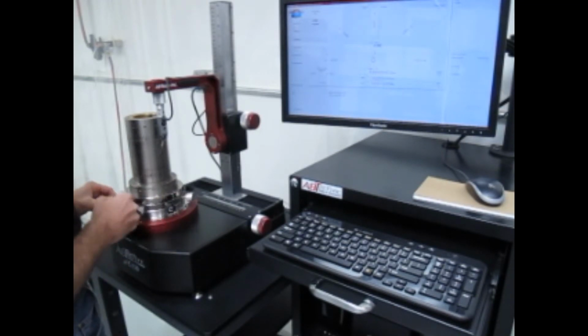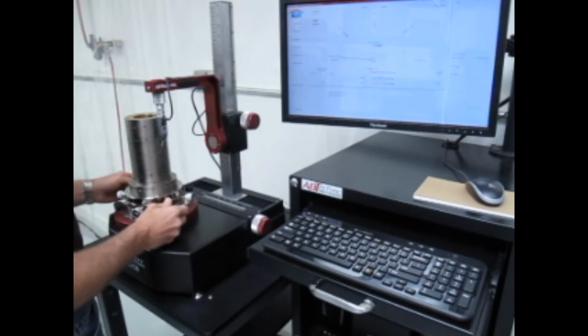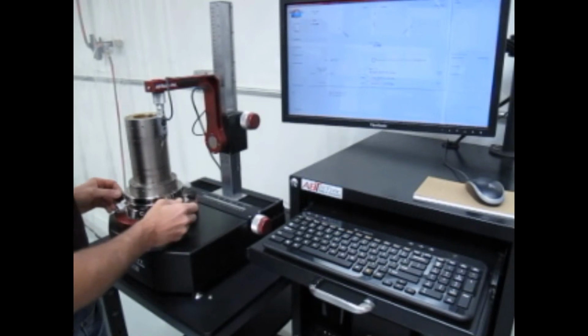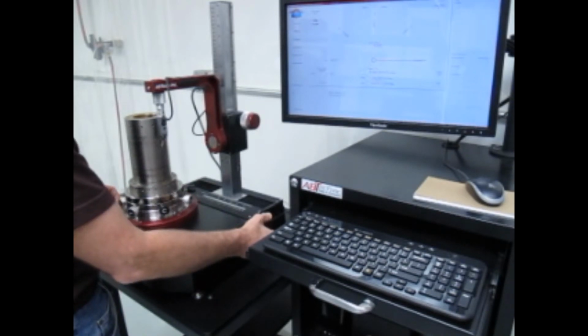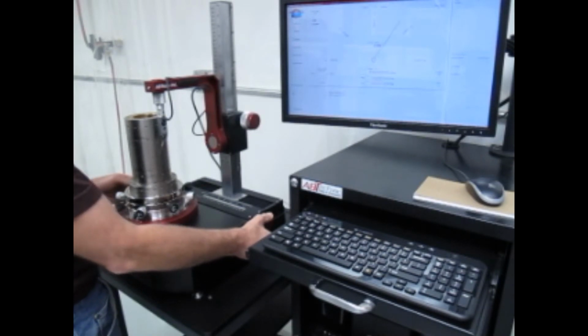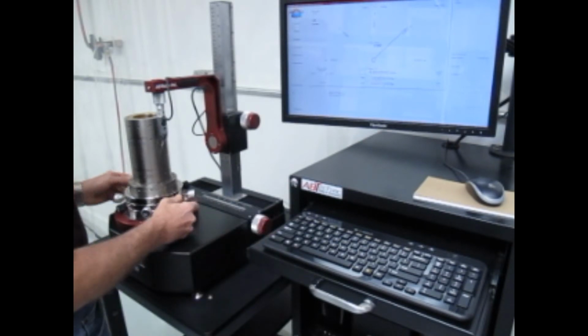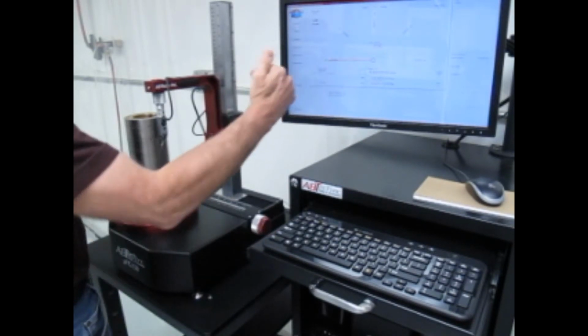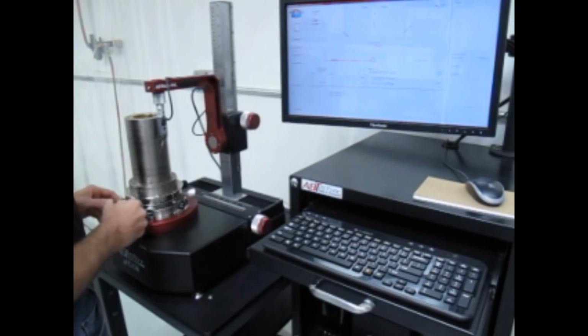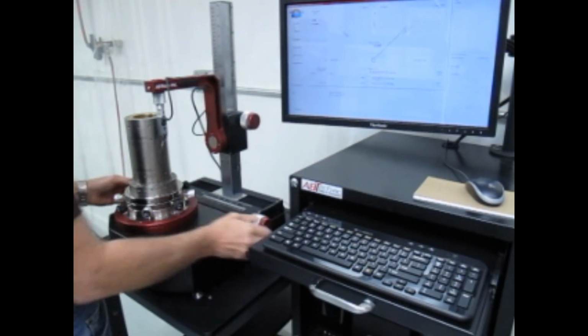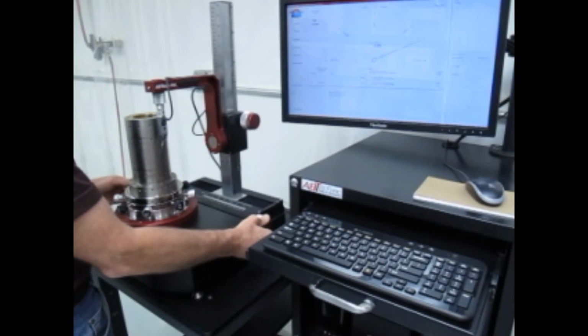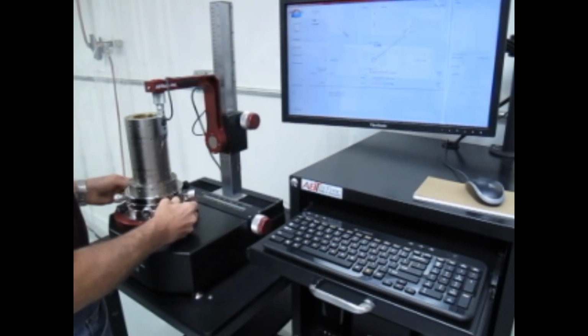And then I'm going to rotate, okay, and you can see that I went too far, so I'm going to go to the other end and bring the probe back using the stage as opposed to the tilt and centering, so that I don't pin on that end, I'm still on scale, but I'm still off scale on the other end. So I'm going to do the same thing: maximize the high point on the scale, translate the stage. I'm not going to go as far this time.